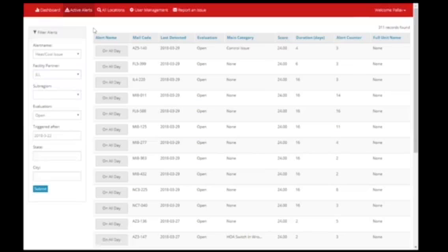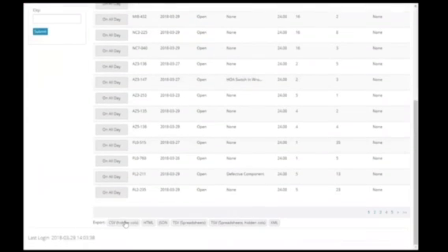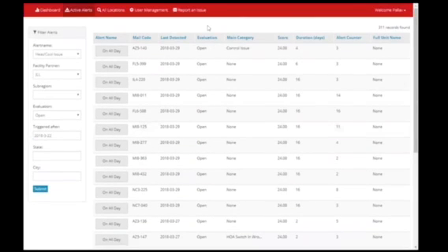Same with lighting issues, which they often run into when the override switch is just left on, for example. There they have a tolerance: if the lighting alert lasts more than 7 days, it creates an escalation within the bank. If it fixes itself within 7 days, then they don't really act upon it. But if it's been on more than 7 days, they'll go talk to the facility partners or shoot out emails. They use this system to export these alerts and manage them within their own work order management system beyond that.